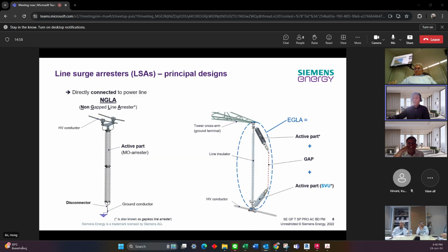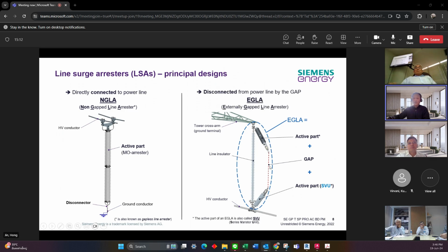Moreover, if we are using line surge arresters, basically we have two designs. One is the non-gapped design, the non-gapped line arrester, NGLA. The other is EGLA, externally gapped line arresters. On the left and on the right side, you can see the difference. NGLA is non-gapped, which means one side is connected to the high voltage transmission line, and the other side is connected through a grounding conductor and a disconnector to the grounding point of the tower body. The right side is EGLA, the externally gapped line arrester, which means we have one or two surge arresters as the SVU. SVU is the abbreviation of series varistor unit, and the SVU can be two parts or one part, of different designs.